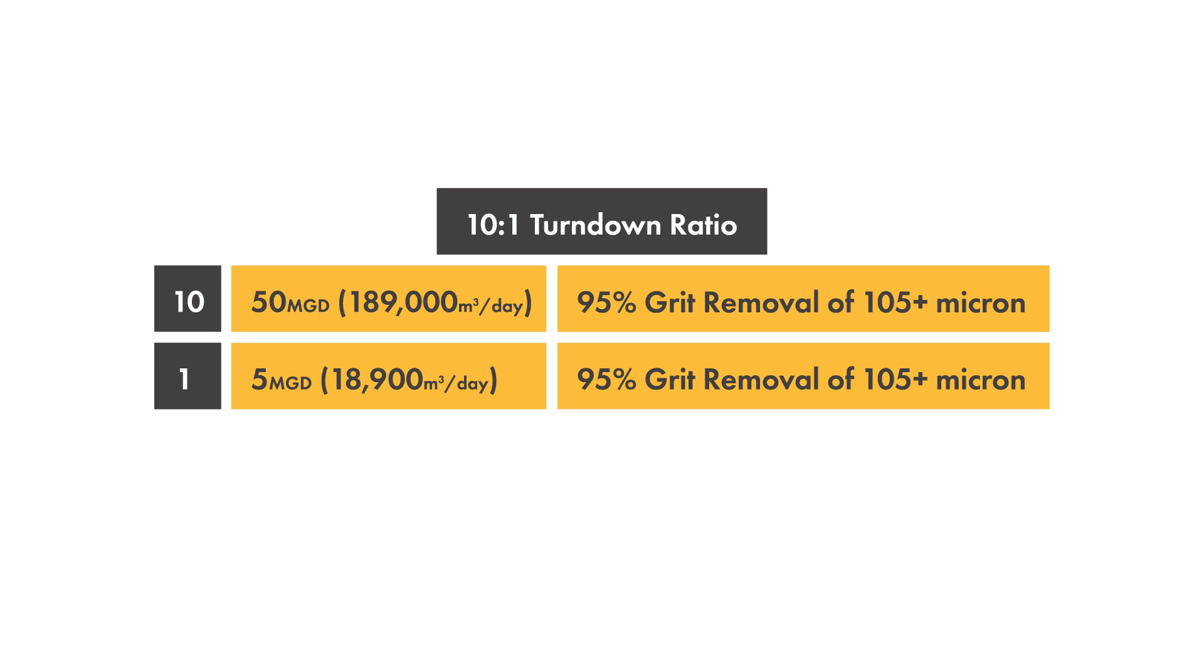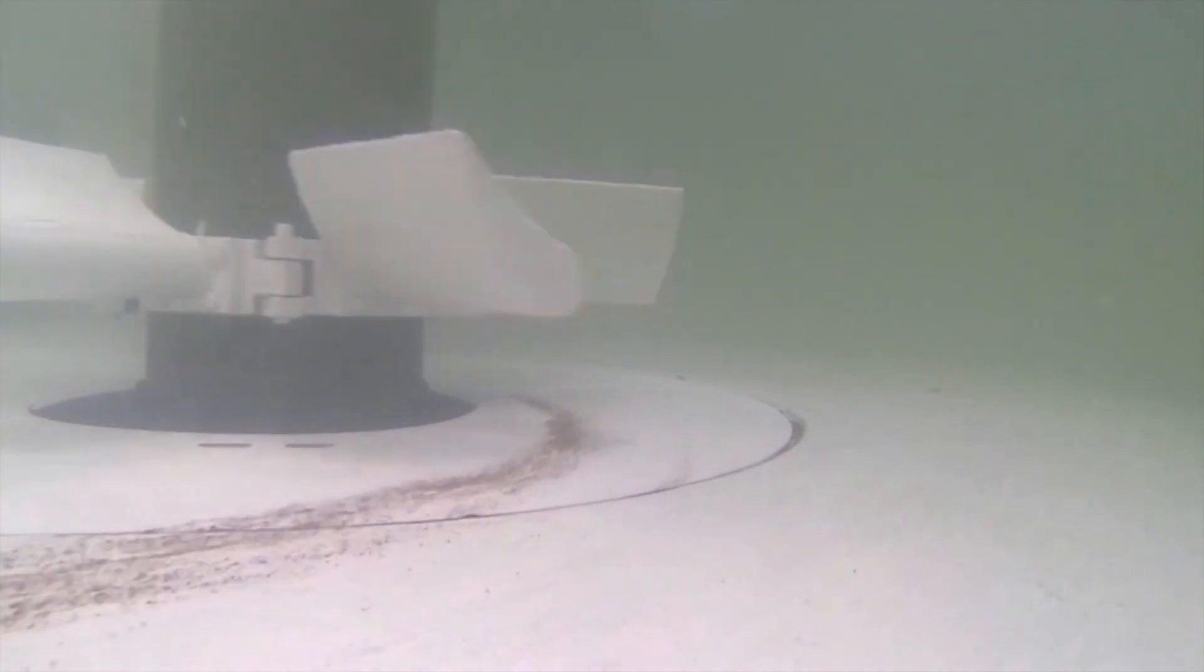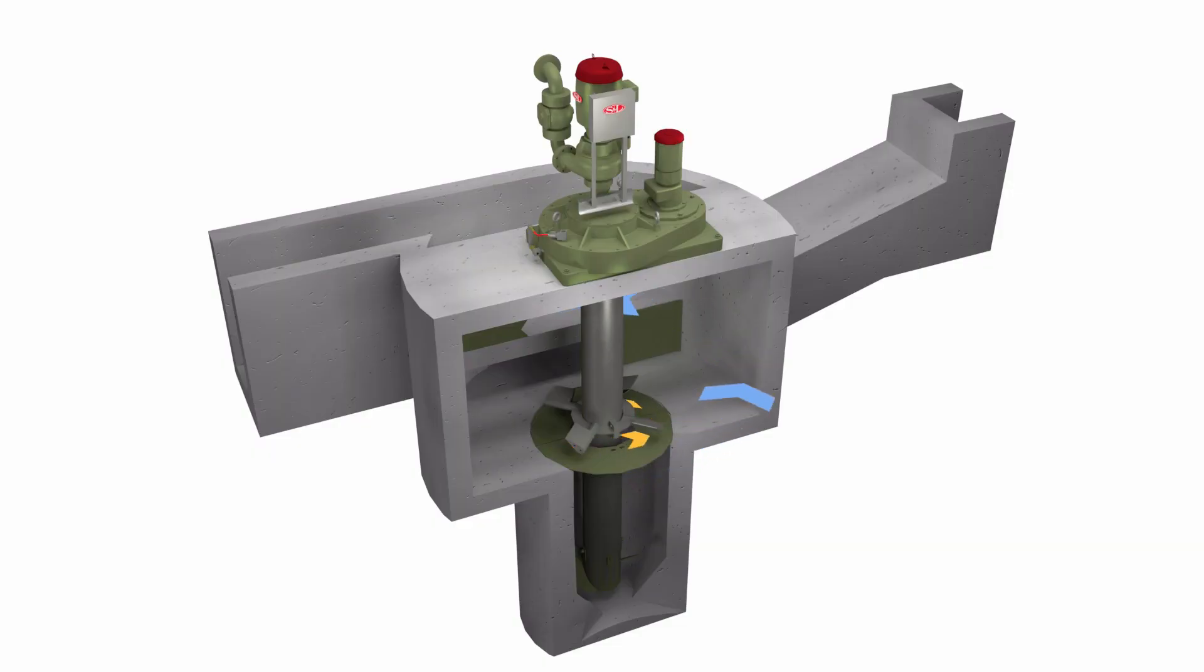The axial flow propellers sweep grit along the floor in a moving bed towards the hopper opening and also lift the organics back into the flow to continue moving them to the next stage of treatment.